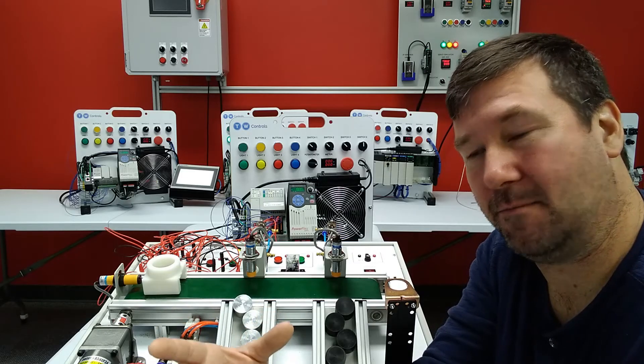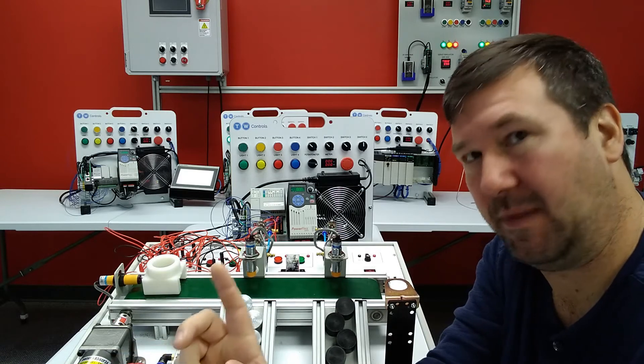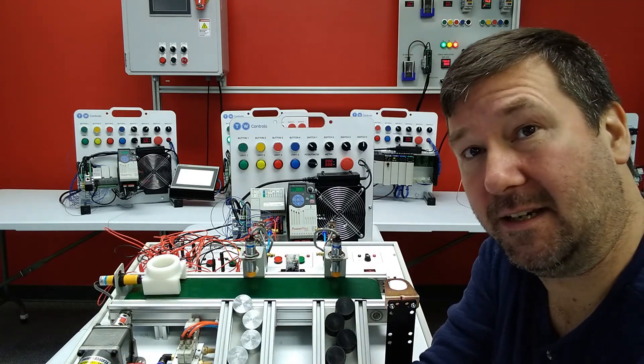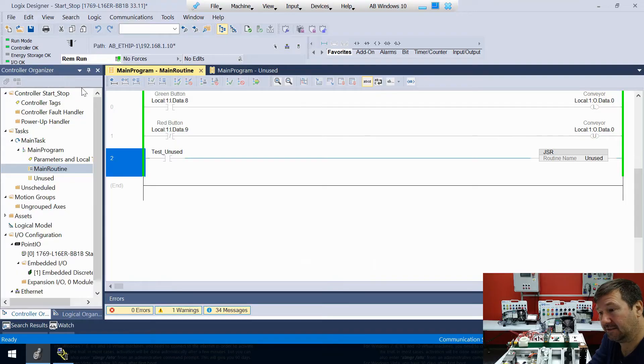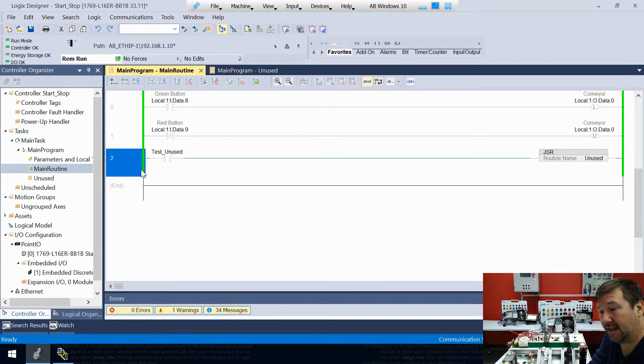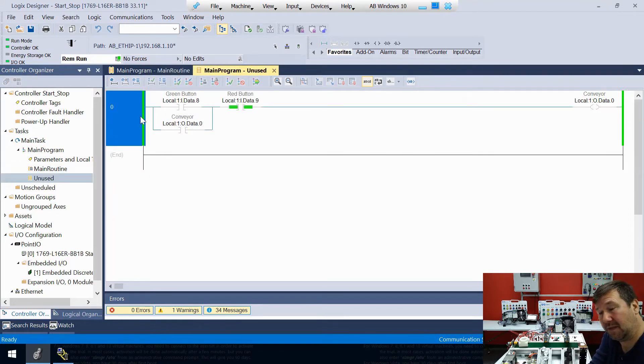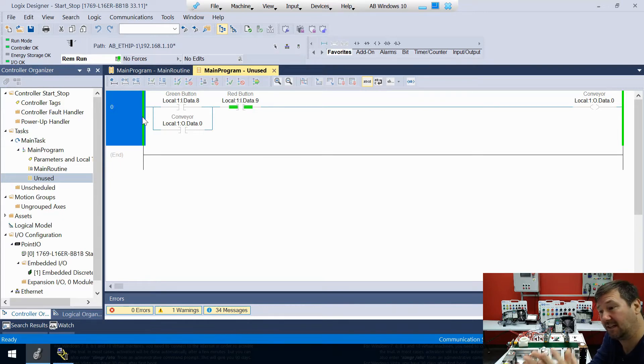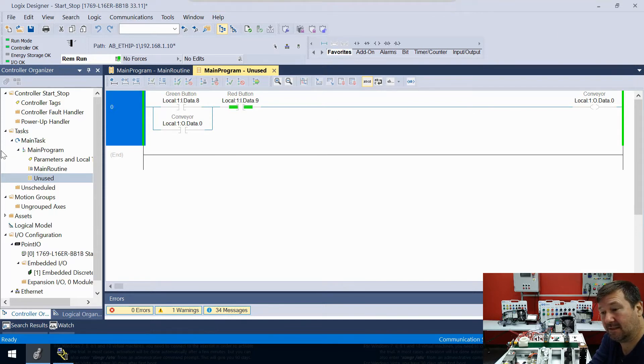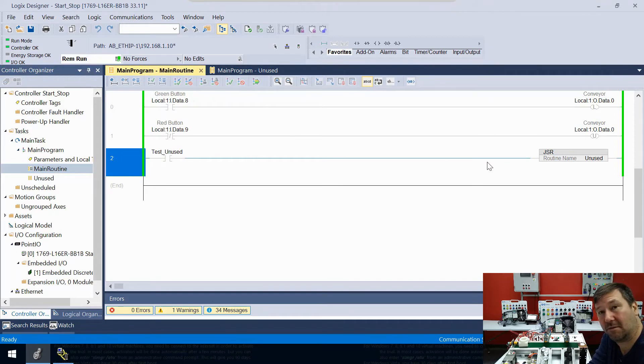I want to make sure you see a big difference in how these programs look. The test unused rung could be called, so it has the green bars — and the JSR rung now also has green bars. The green bars mean that the routine could be called, not that it is currently being scanned. Currently this is not being scanned because we have false conditions going to our JSR.